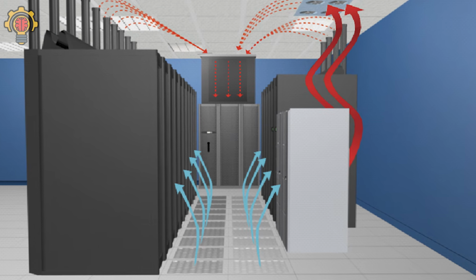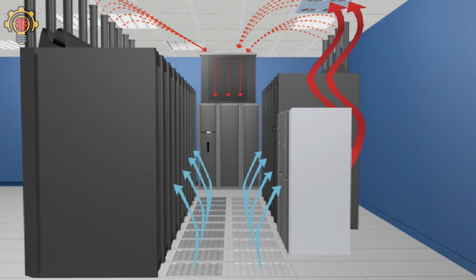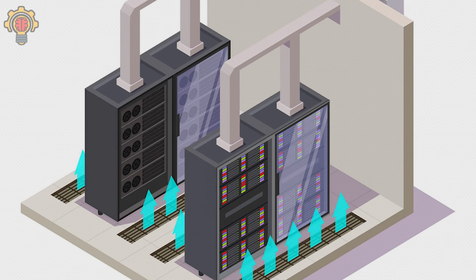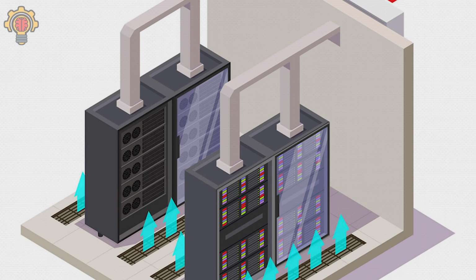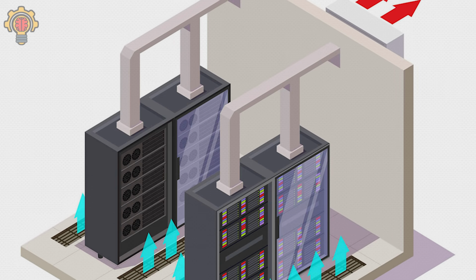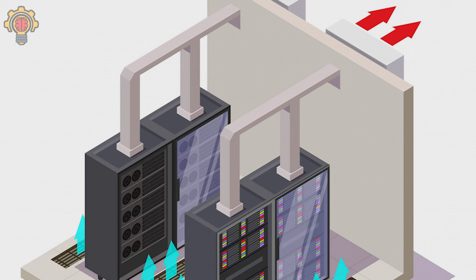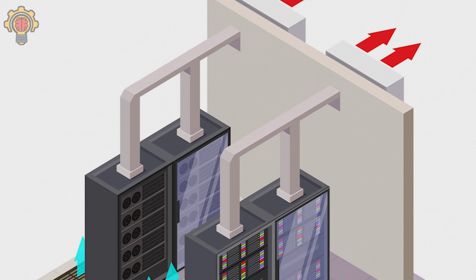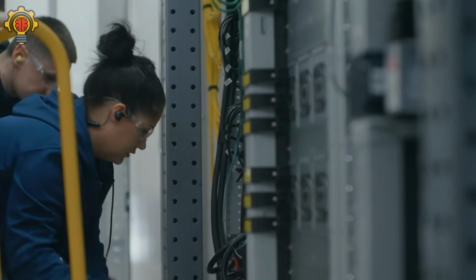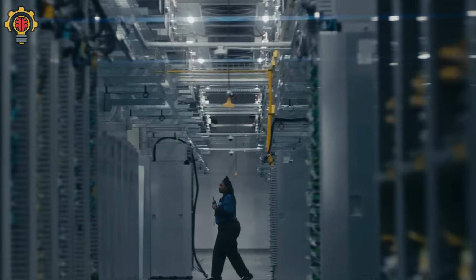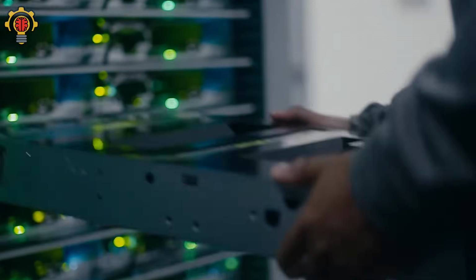For years, this became the standard design. But as server densities increased, engineers started noticing major inefficiencies. Cold air had to travel too far, energy usage increased, and hot air still mixed with cold air inside the room. That led to one important idea. Instead of cooling the entire room, why not bring cooling directly to the heat source itself? And that idea created in-row cooling systems.